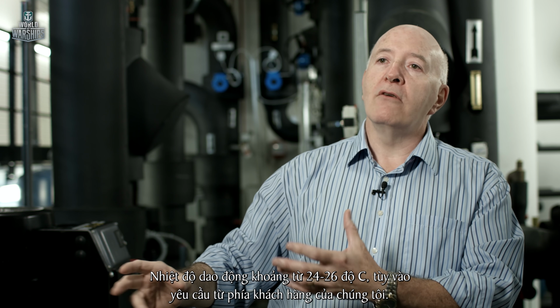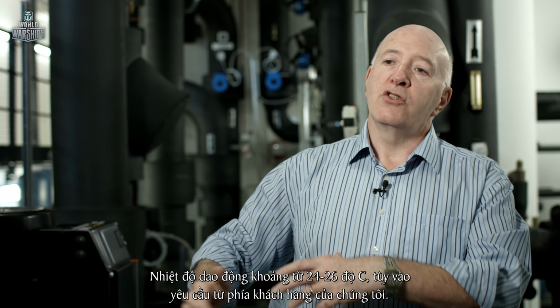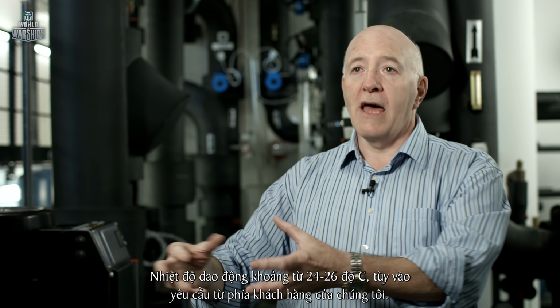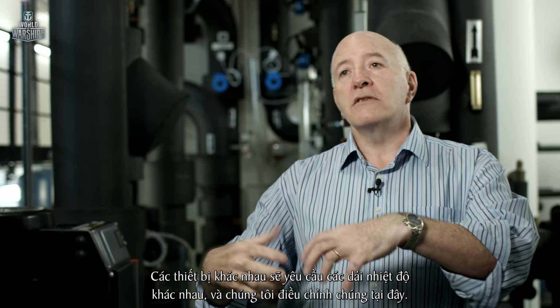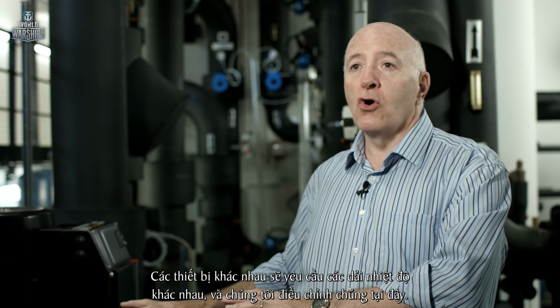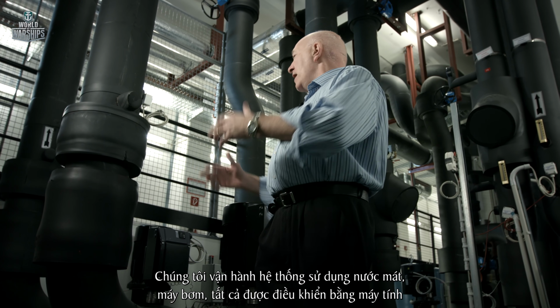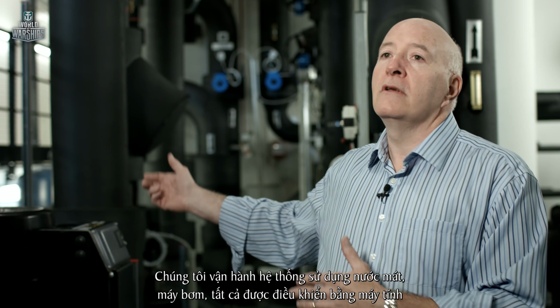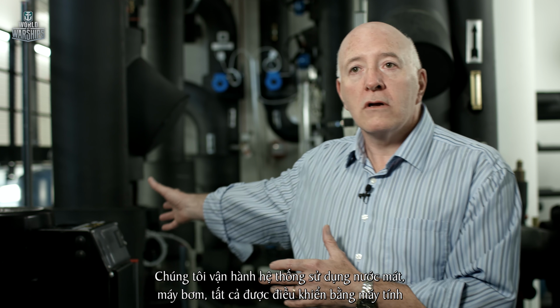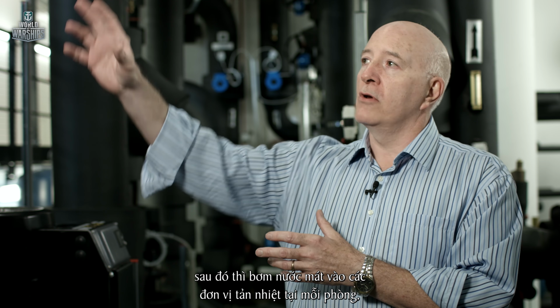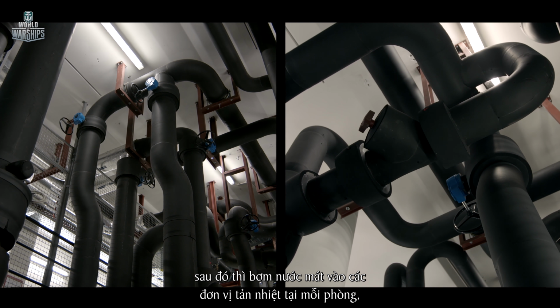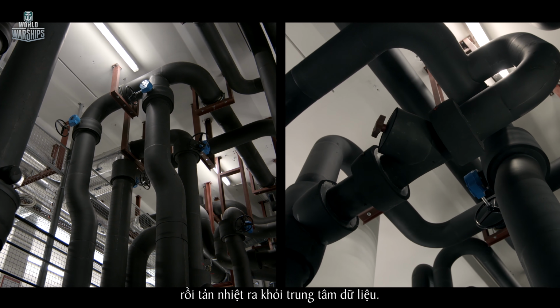A temperature of around 24, 25, 26 degrees, depending on what the client wants in that room. Different equipment requires different temperatures, and we can control it all from here. We do that using chilled water and pumps, all computer controlled, which push chilled water through the cooler units in each room to take the heat away from the data center.